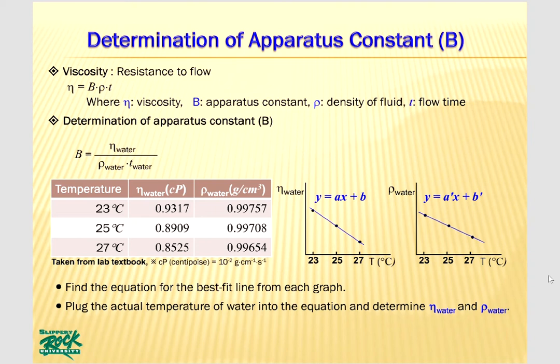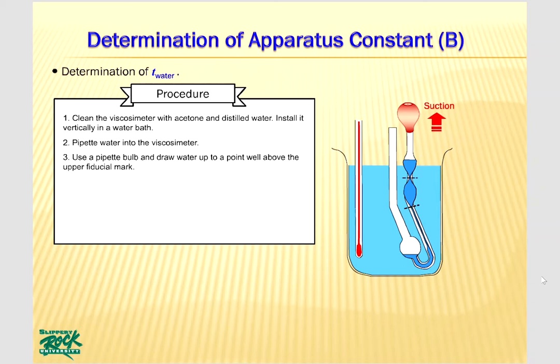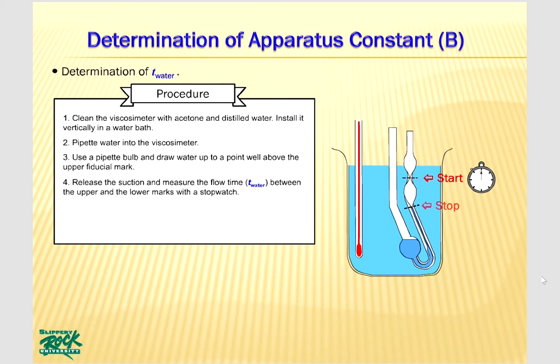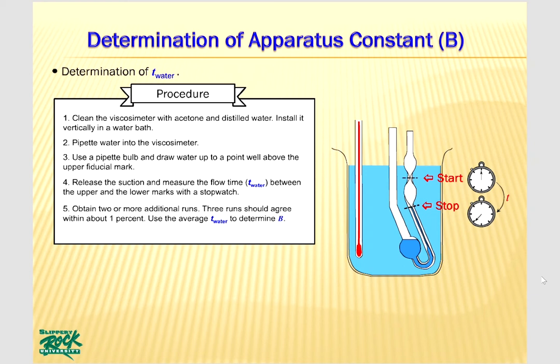Clean the viscosimeter with acetone and distilled water. Install the viscosimeter vertically in a water bath. Pipette water into the viscosimeter, use a pipette bulb and draw water up to a point well above the upper viscosimeter mark. Release the suction and measure the flow time between the upper and lower marks with a stopwatch. Obtain two or more additional runs; three runs should agree within about 1%. Use the average flow time of water to determine B. Since you have determined the viscosity and density of water and measured the flow time of water, you are now ready to determine the apparatus constant B.